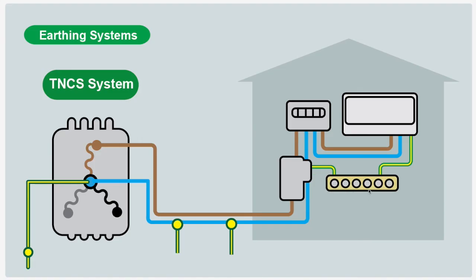This can all become live. It could energize all the protective conductors, your main earthing terminal - everything connected to the earthing point could become live. That's why there are special considerations. They call it protective multiple earthing as well.